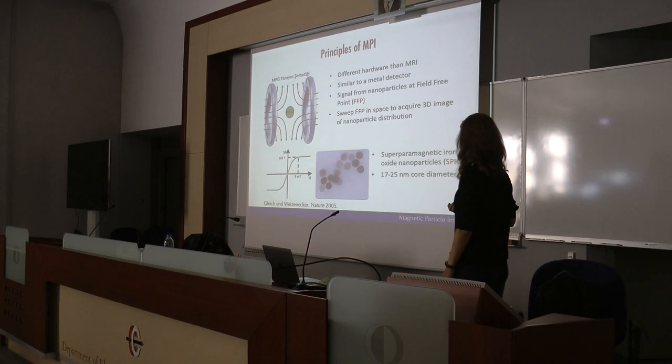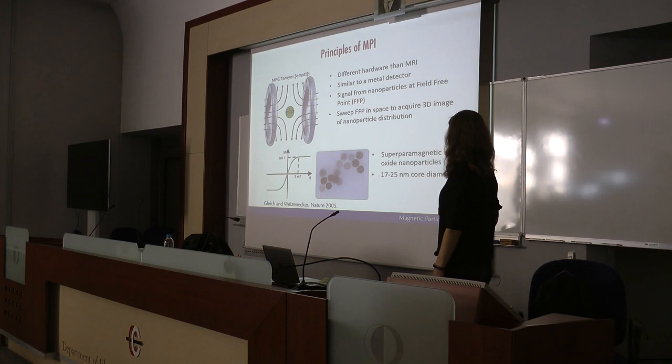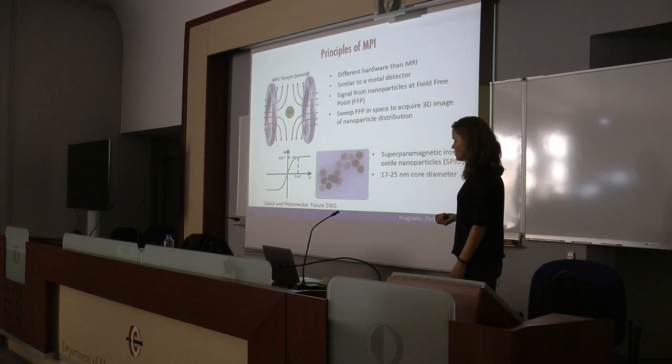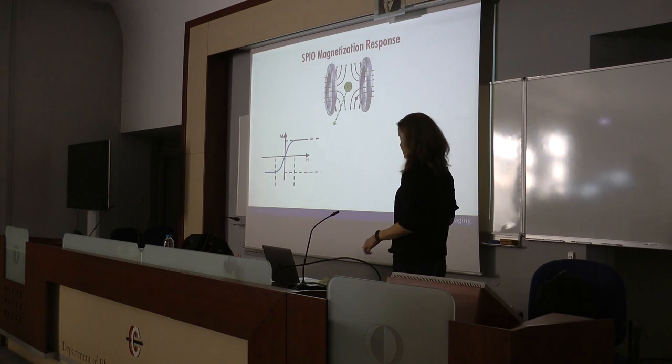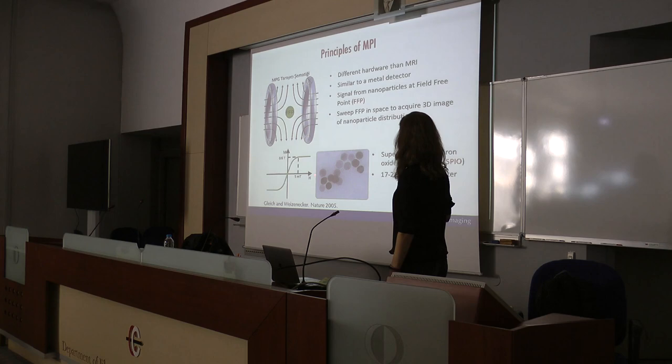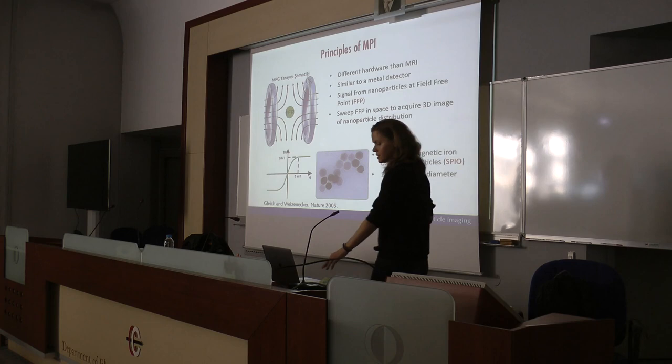The nanoparticles used are superparamagnetic iron oxide nanoparticles known to be safe for use in humans, with typical core sizes from 17 to 25 nanometers. When placed in the MPI scanner, these nanoparticles have a nonlinear magnetization curve — if the applied field exceeds a certain value, the magnetization of the nanoparticles saturates in both directions.